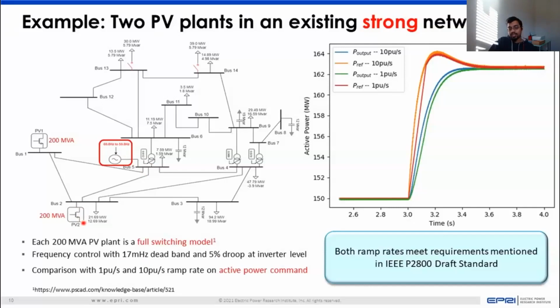how the response of the control of the plant would change when observed at its terminal for two different ramp rates of 1 per unit per second and 10 per unit per second. So these are ramp rates that are set on the active power command of the plant. Now note that these plants are very conventional kinds of plants, so they have to measure the frequency, they need to sense what is happening with respect to the frequency, they need to filter it, they need to act upon that measurement, and only finally can they change their active power command that's given to their inverter, and then they have to act upon it in terms of the current control and things like that.